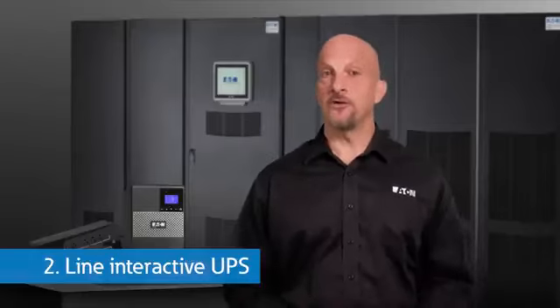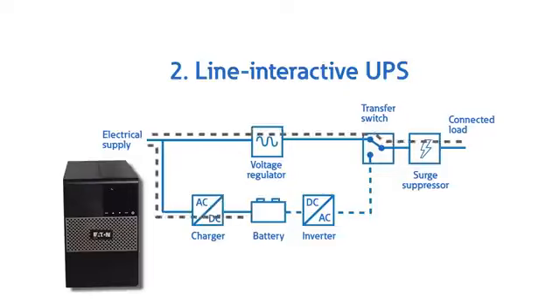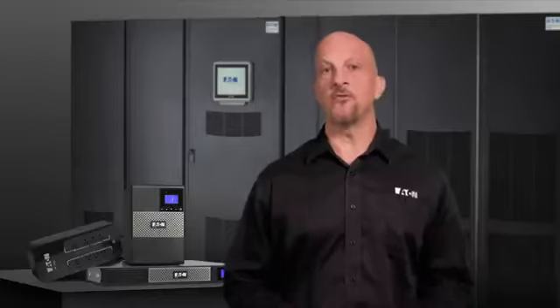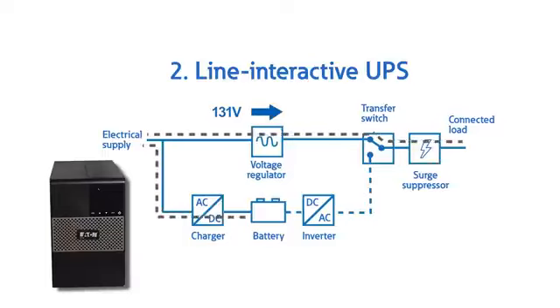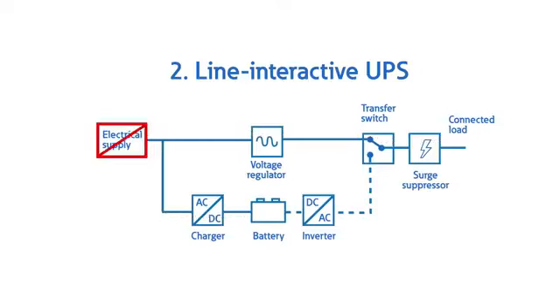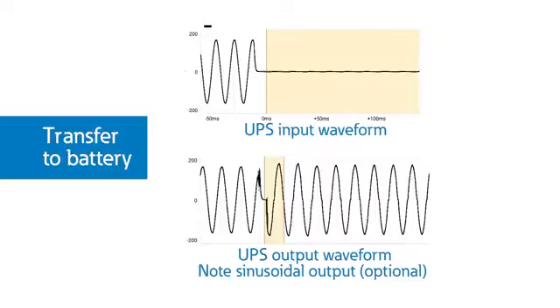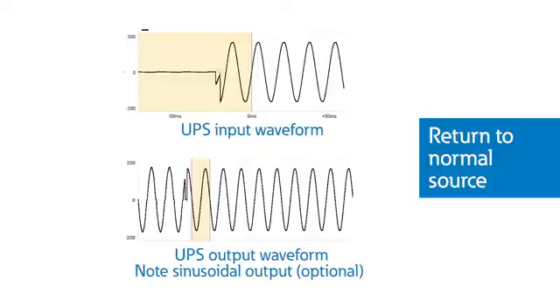Line interactive UPSs are very similar to the standby UPSs, but they also provide long-term voltage regulation. For example, if the voltage in your house was running at 106 volts instead of 120, the line interactive UPS would regulate the voltage back to a level very close to 120 volts. These units can also provide overvoltage protection, meaning that if your voltage was 131 volts, it would pull the voltage back down to 120 as well. However, if the voltage exceeds a significant undervoltage or overvoltage, or is fully interrupted, the UPS would switch over to the battery just like the standby UPS. Again, this would all happen very quickly before most loads would even know that the power source had been transferred.